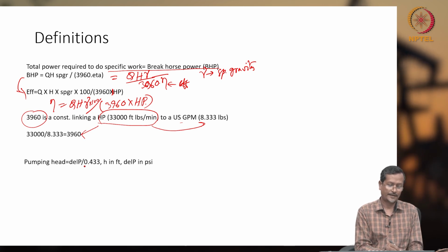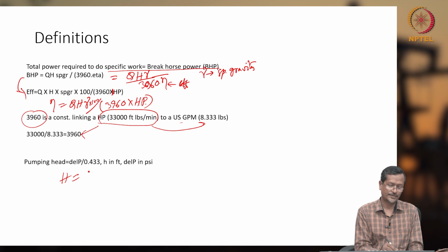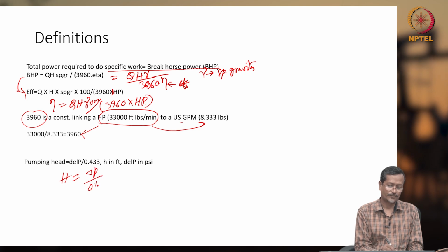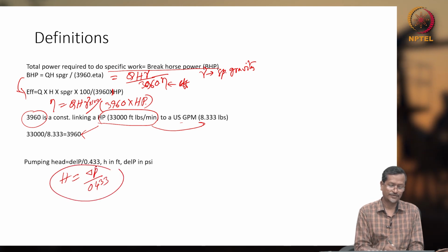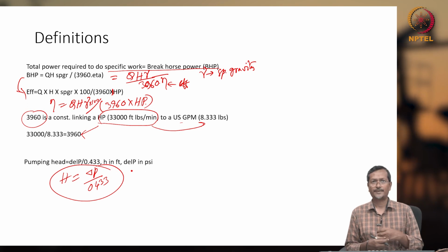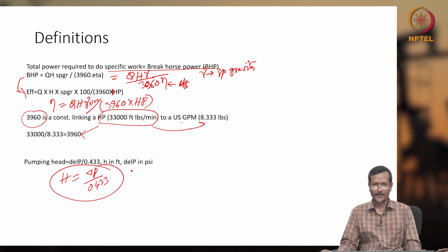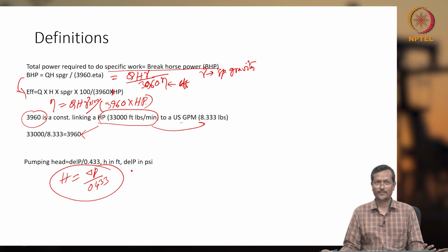And pumping head calculation is, head equals delta P divided by 0.433, okay. H is in feet, delta P in PSI. So you have to remember units every time. If you are forgetting units, there will be difficulty when you are solving the problems.